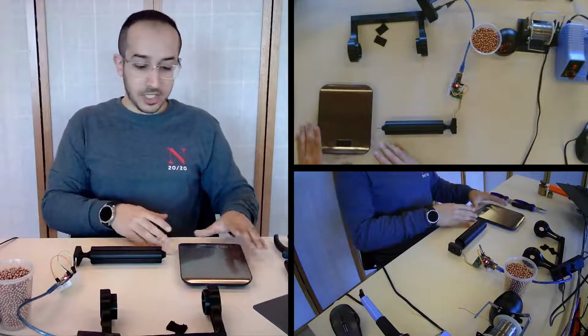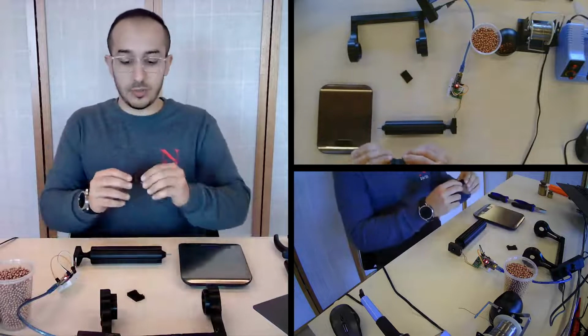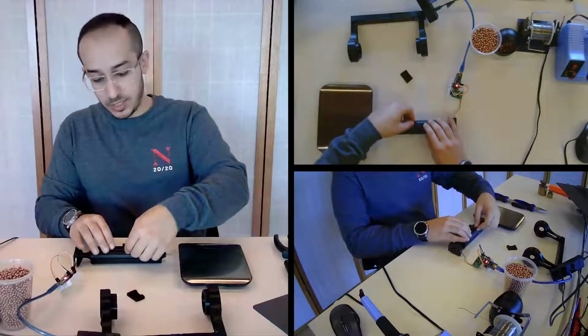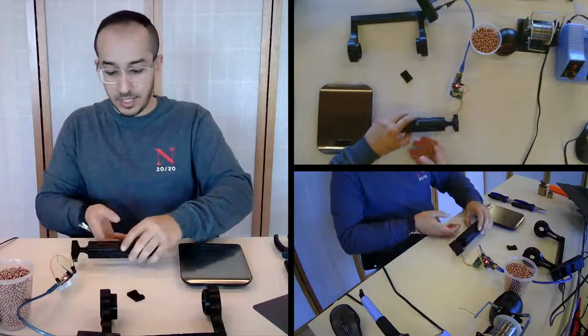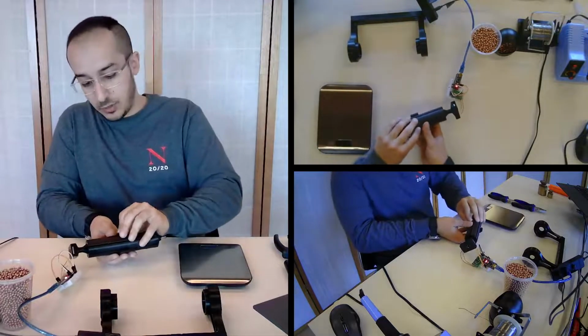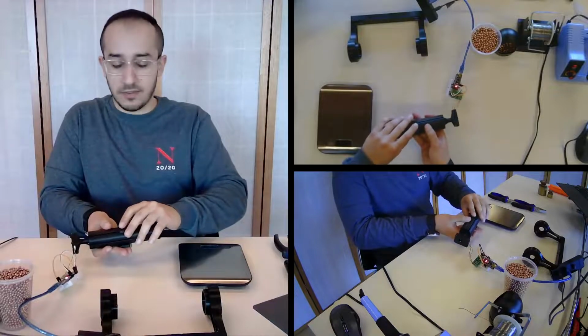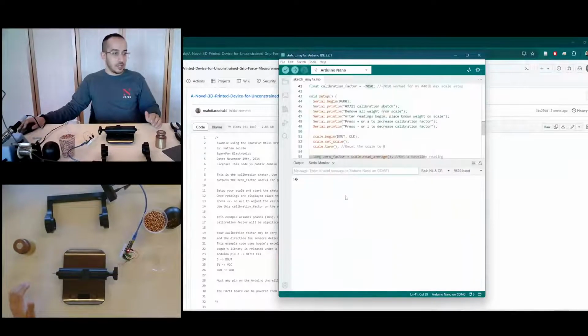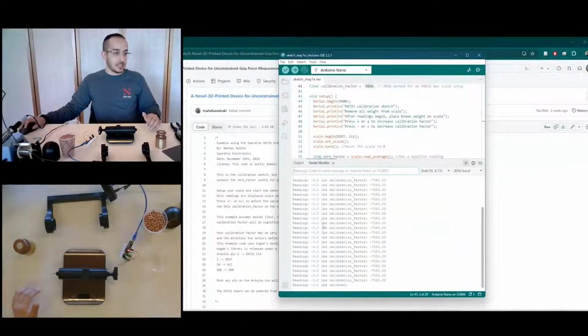So with the kitchen scale, what I will first do is take these two load applicator plates and place one on the top and then another one on the opposite load plate. This just gives us a flat surface to apply load on. Okay, now we can click on serial monitor and we'll get the sensor output. It's right now saying the output is in pounds, but of course you can change this to whatever units you want. And in fact, I will change it to grams because the kitchen load cell I'm using is in grams. And the calibration factor is what we will change to calibrate the sensor.